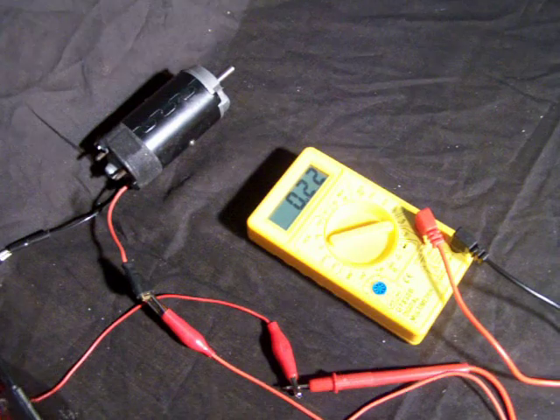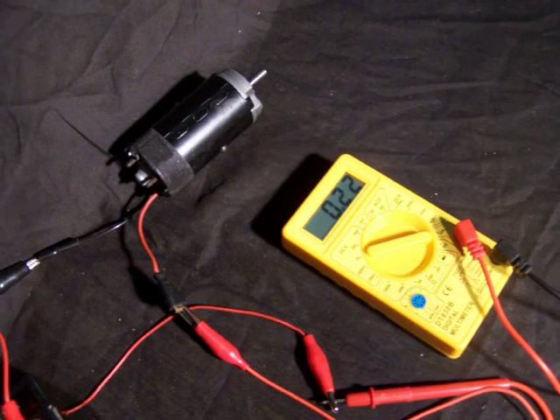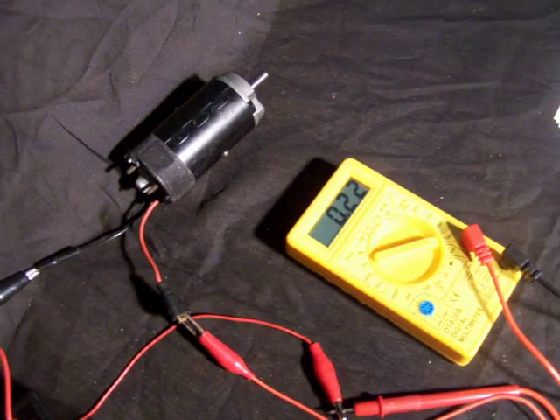The motor immediately starts running as you can read the amps from the meter screen. This is a no-load amp reading.